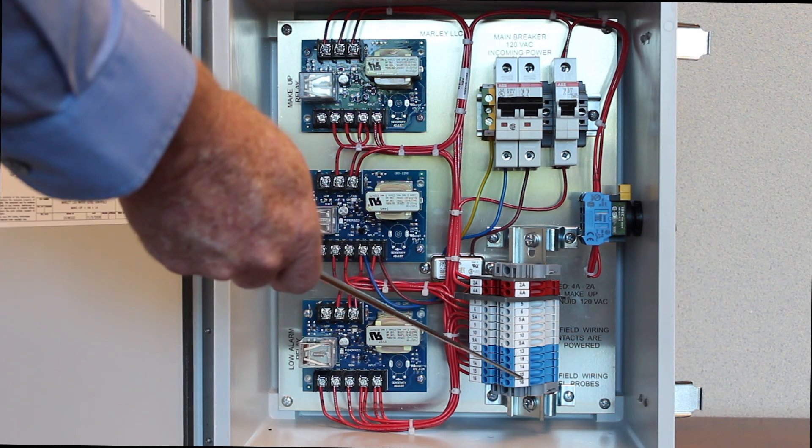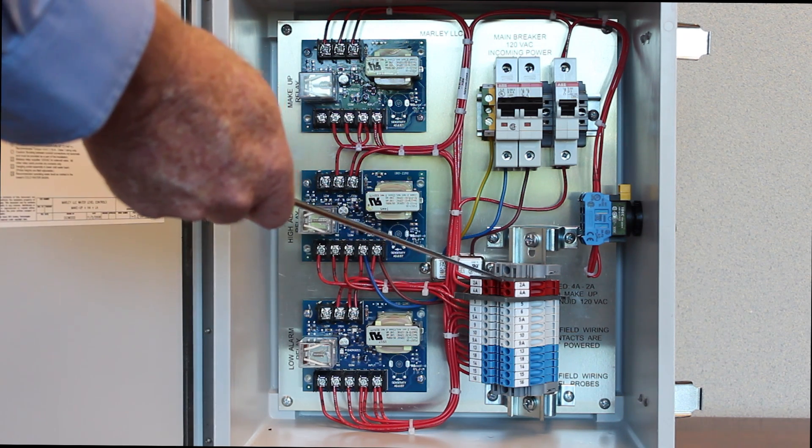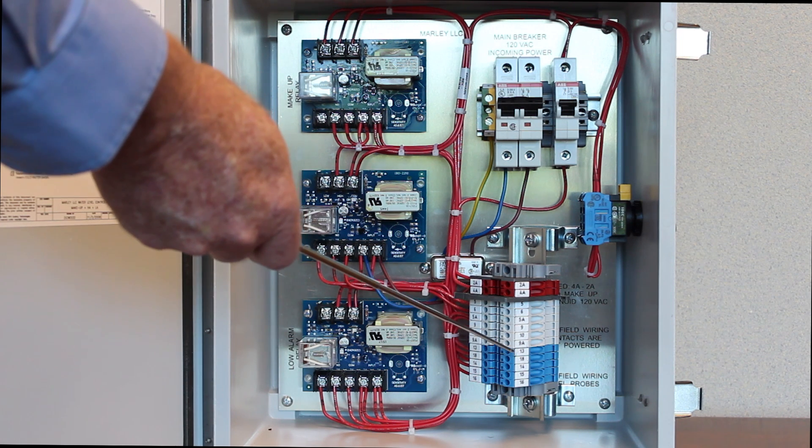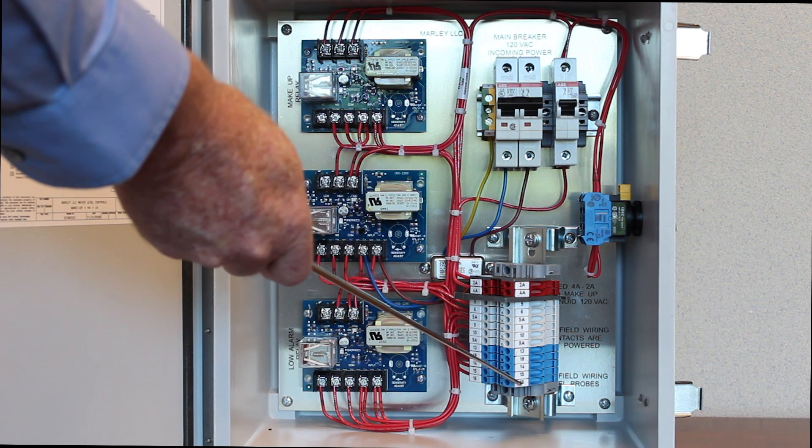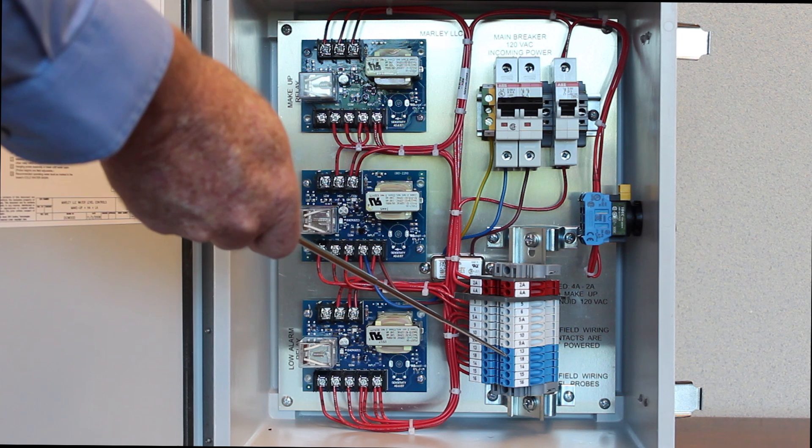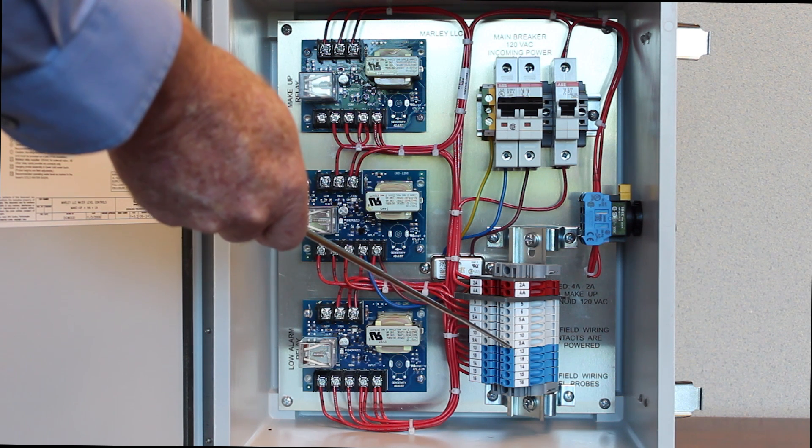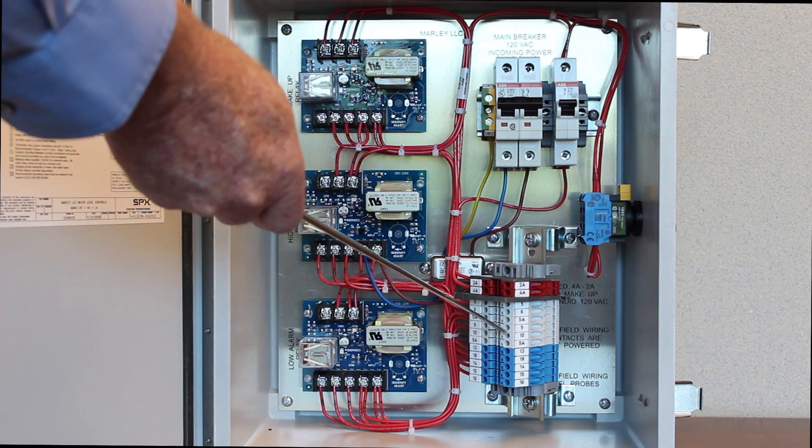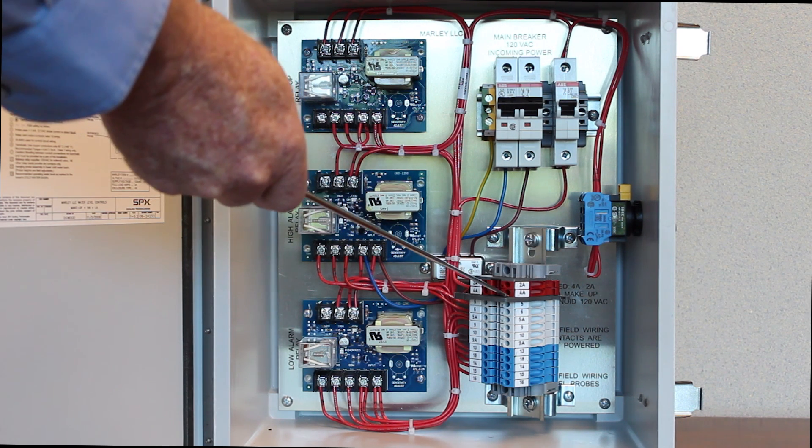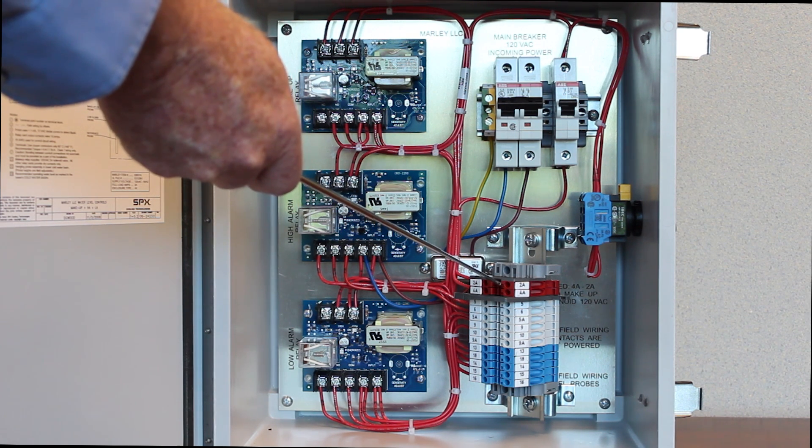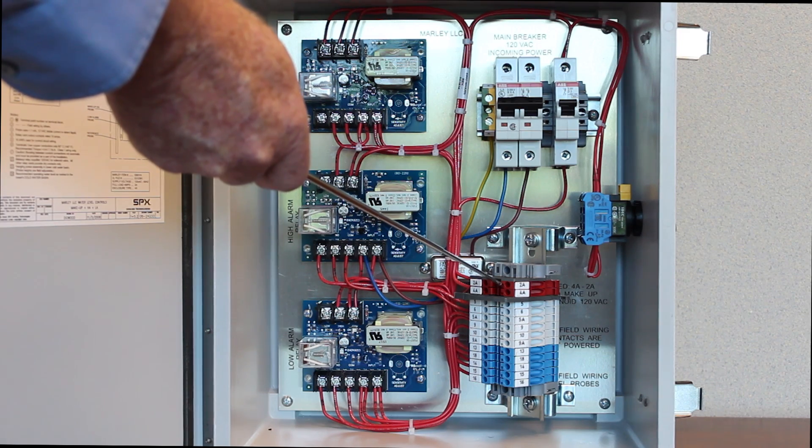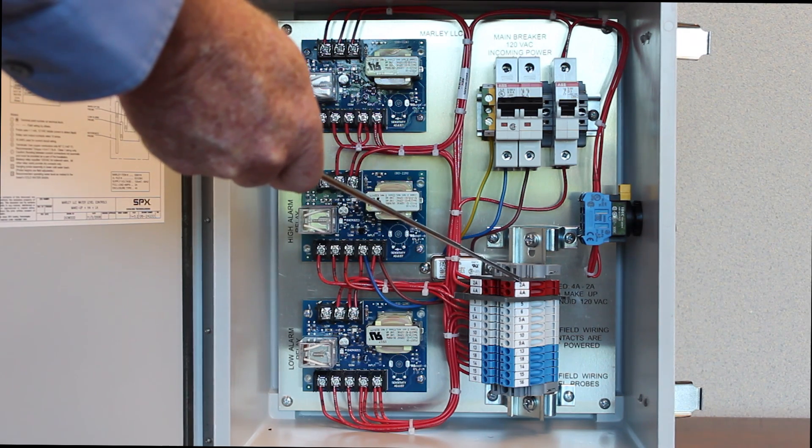Over here to the right we have a user terminal strip. The user terminal strip is used by the electrician to terminate the water level probes on the blue terminal points here, to get the output contacts going back to a building management system on the gray terminal points, and to get 120 volt or 220 volt power out to the solenoid through the red contacts here.